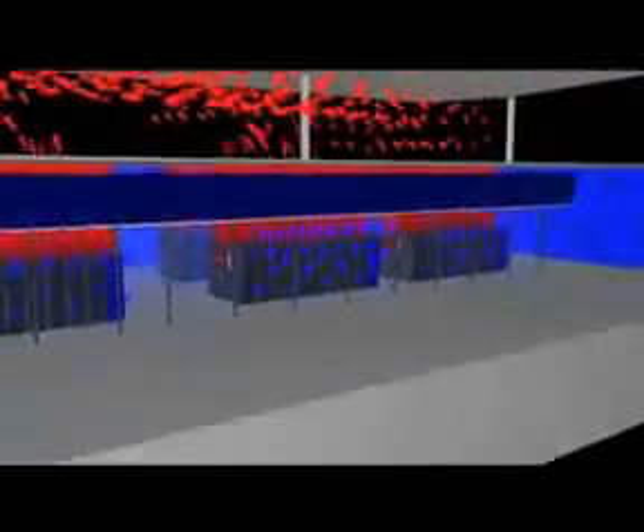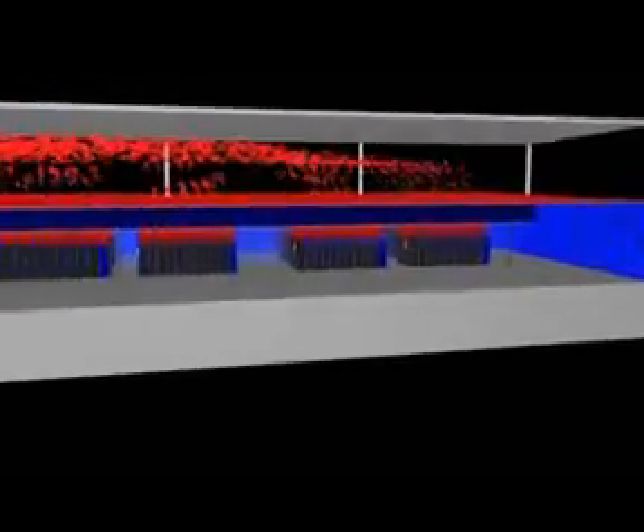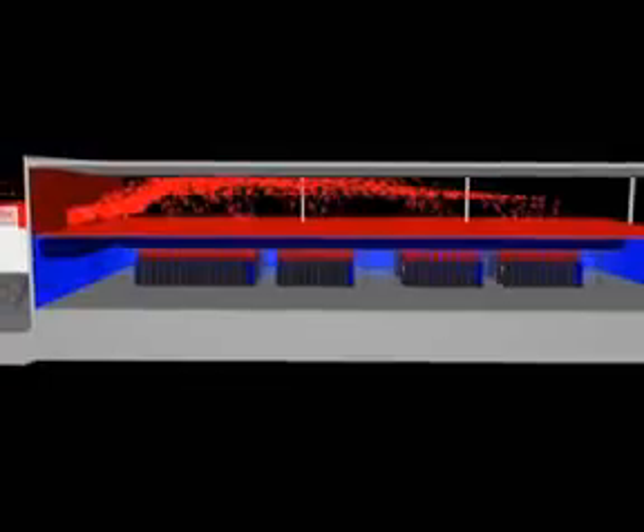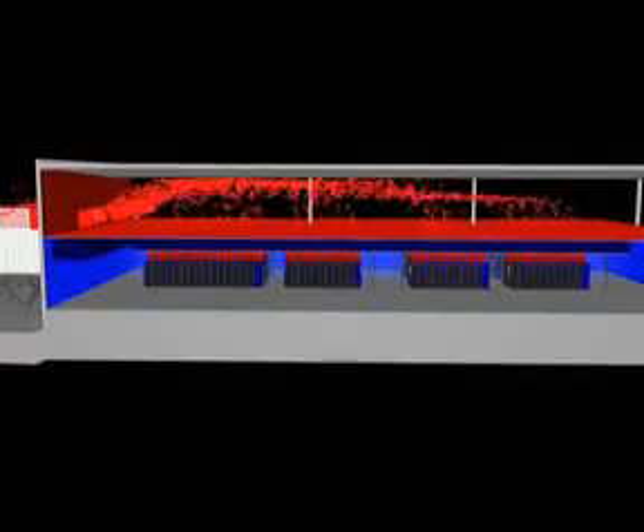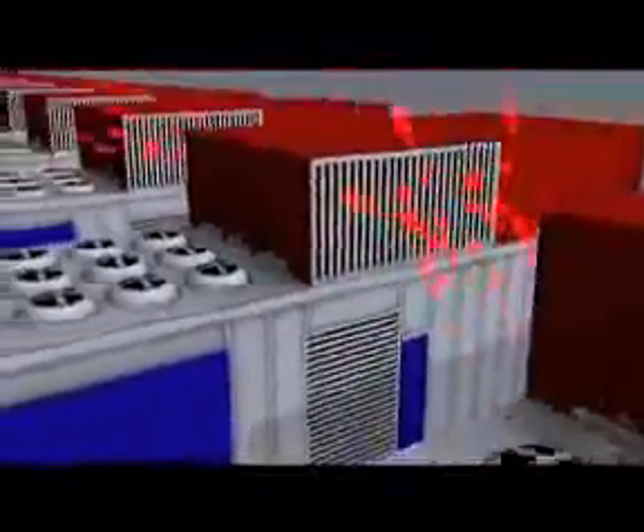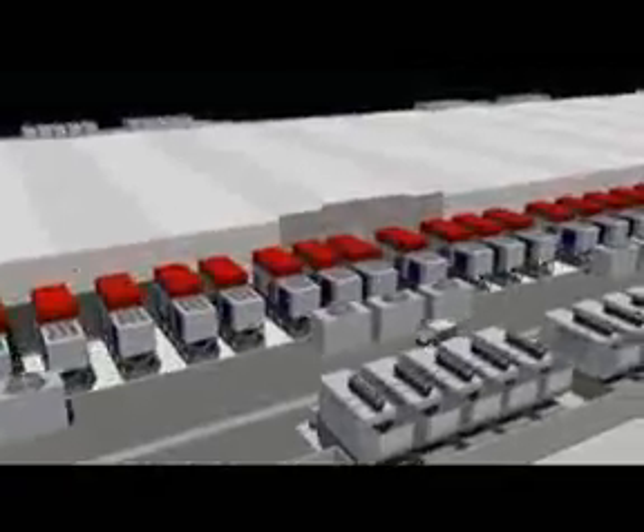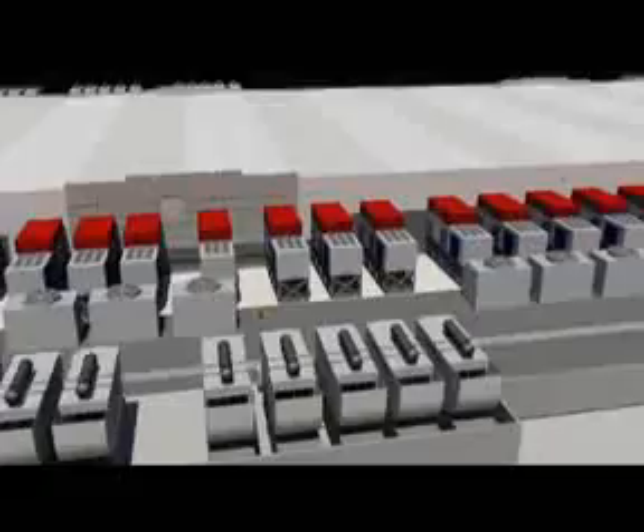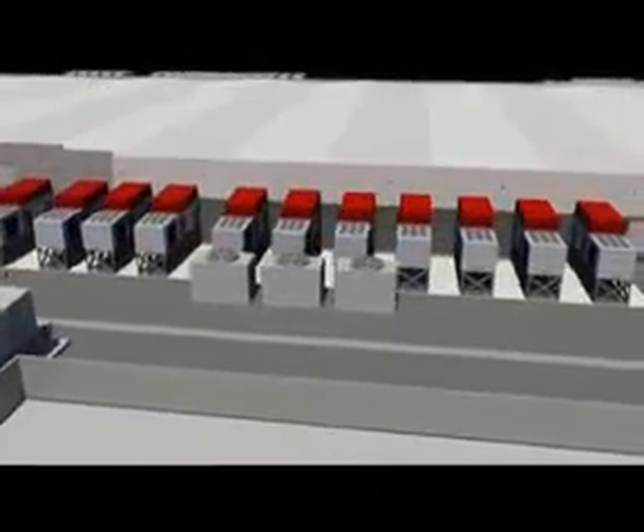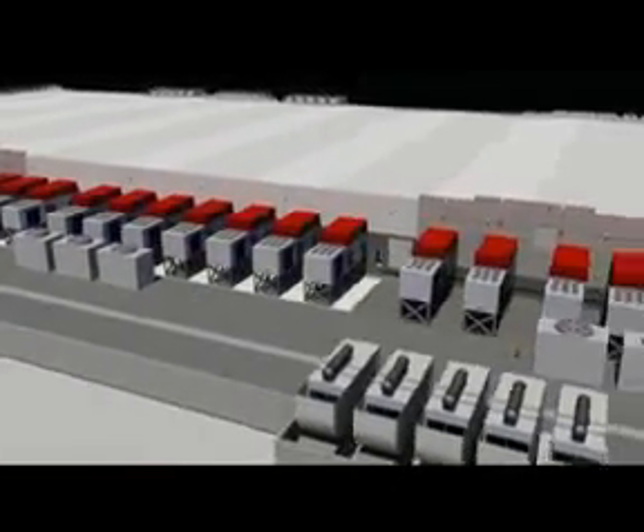If you walk into the room, you're in a basin of cool. The air gets pulled over by the fan units in the server racks, distributed through a hot aisle containment system, and pulled back to a central location where it gets cooled down, recycled, and pushed back out onto the data center floor. To maximize the amount of rentable rack space, Switch placed its air conditioners outside the building. If you look down the side from an aerial view, the whole thing looks sort of like a distribution facility with a lot of semi-trucks backed up to it.